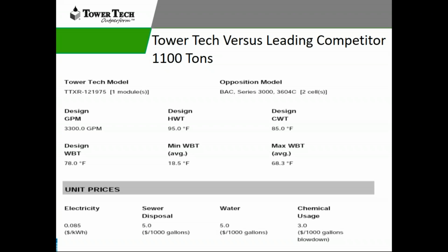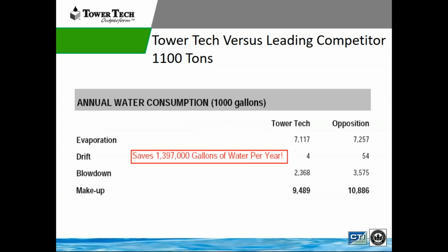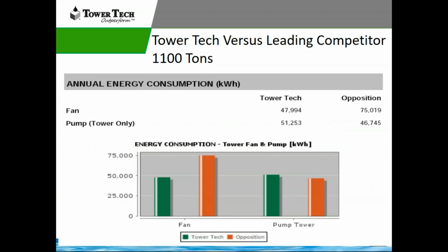So we got to look at an 1,100 ton plant. This is a recent project we looked at where the end user liked the idea of going with the Tower Tech solution. This is an 1,100 ton chiller plant. Again, same energy. Actually, I used slightly less cost for water. In this one, in this particular case, I rounded it at 10 in this example. But in this one, we were saving the end user just under 1.4 million gallons a year of water, okay?